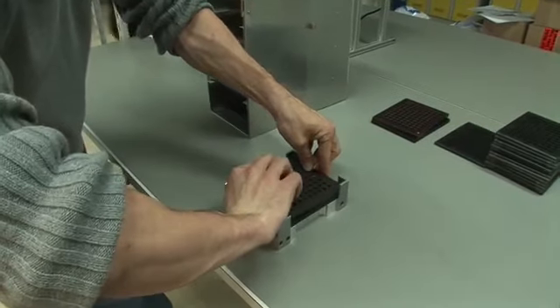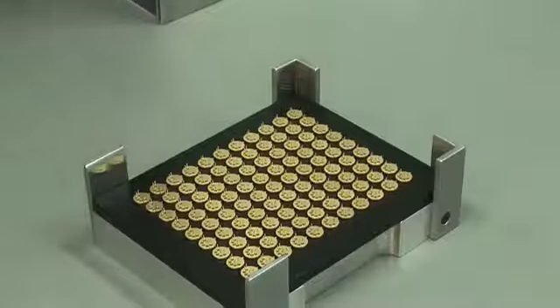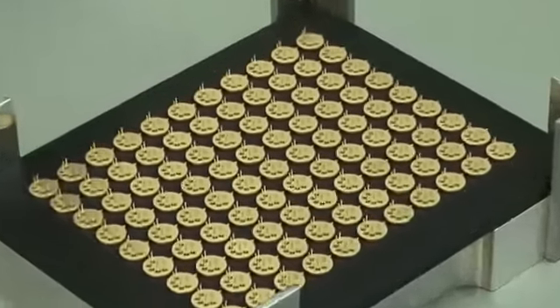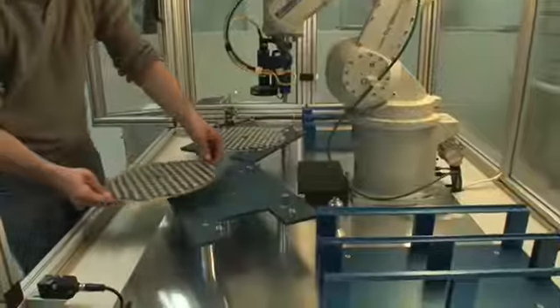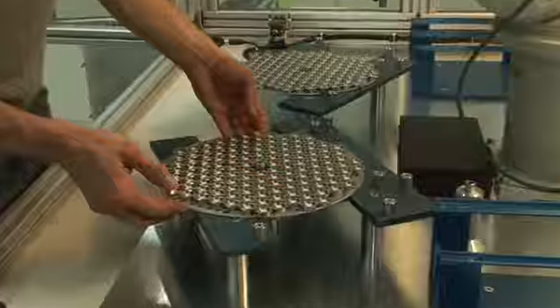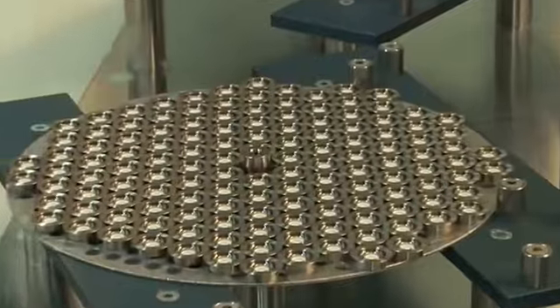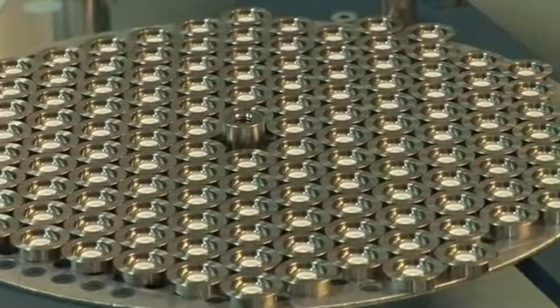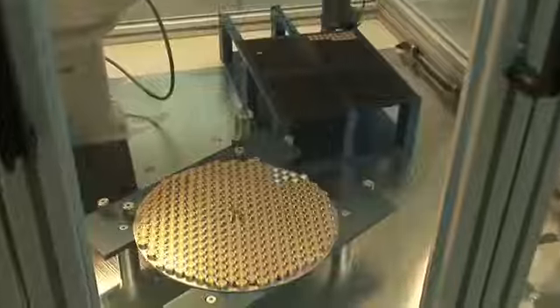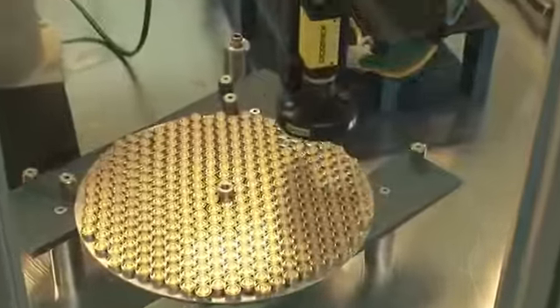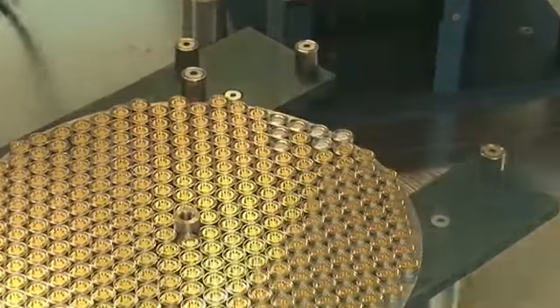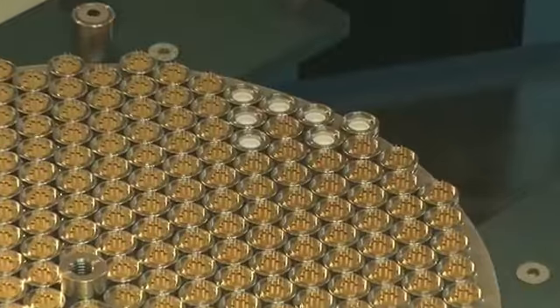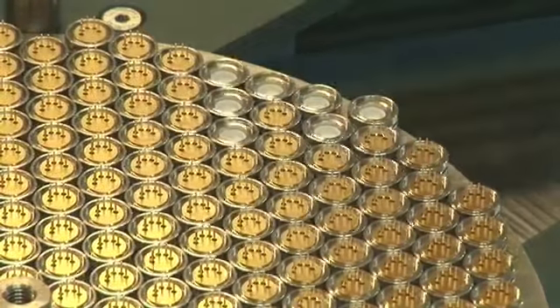As many pressure transducers are exposed to aggressive liquids or gases during their use, the sensitive sensor element is protected from harmful environmental influences by a stainless steel casing. These are generally referred to as insulated pressure measuring cells. A robot grips the sensor element and tests its electrical properties while it's being inserted into the casing.